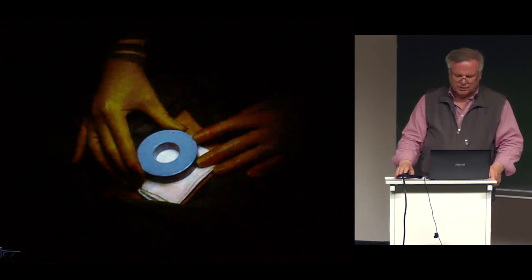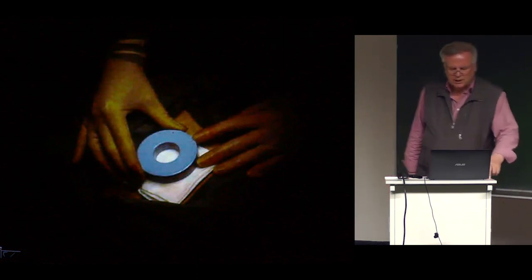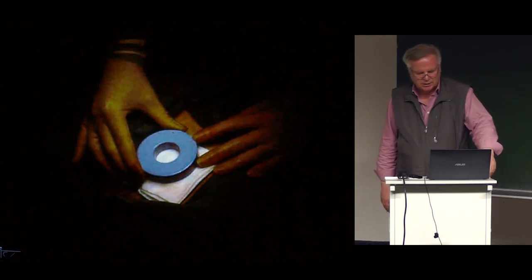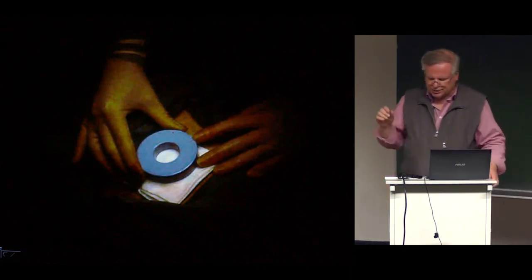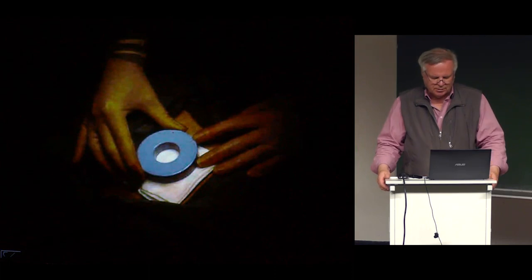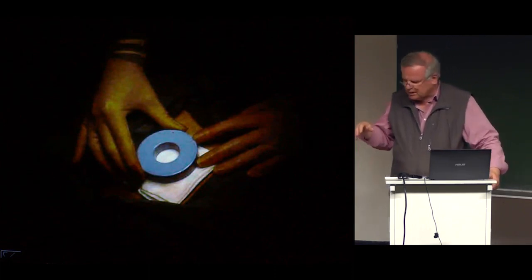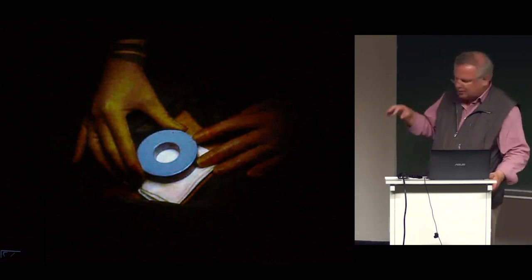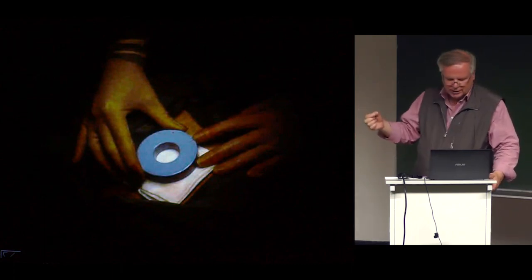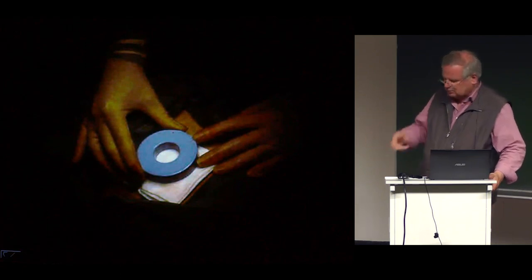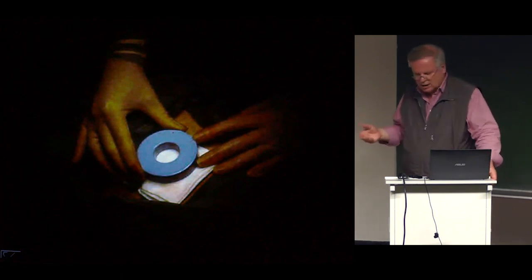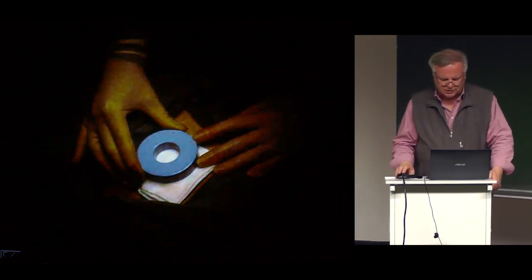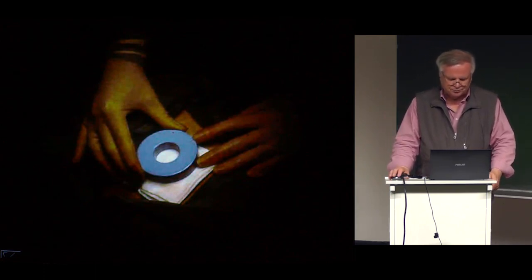Finally, when the new pacemaker is installed, this is a demand type pacemaker. There is a reed switch relay in the pacemaker, so that when placing a permanent magnet above it, it closes the relay and forces it to operate, because if the heart is running normally at that instant, the pacemaker doesn't work. So with this, it is forced to work, and it can be checked that it is working properly.